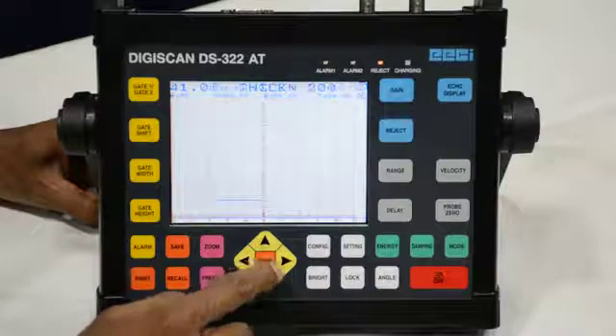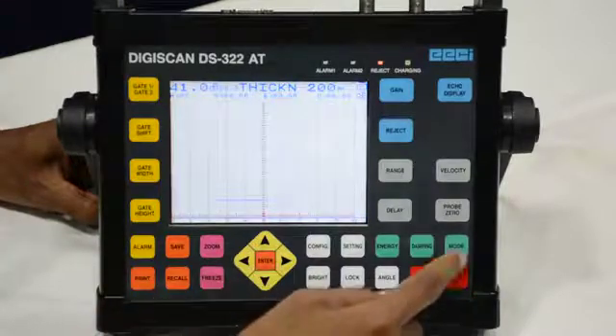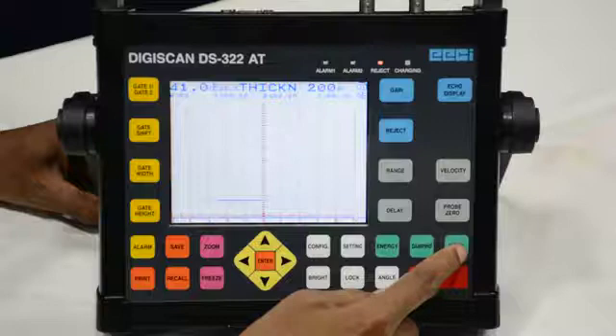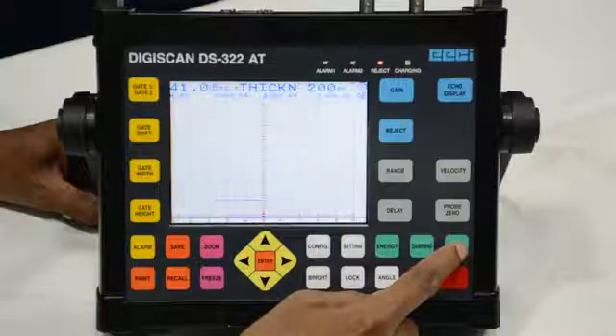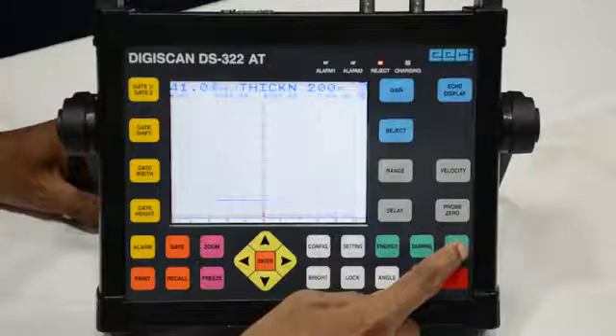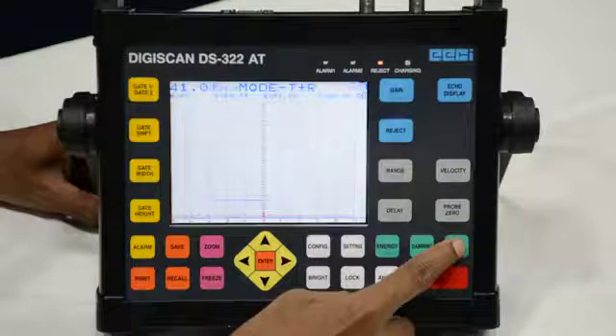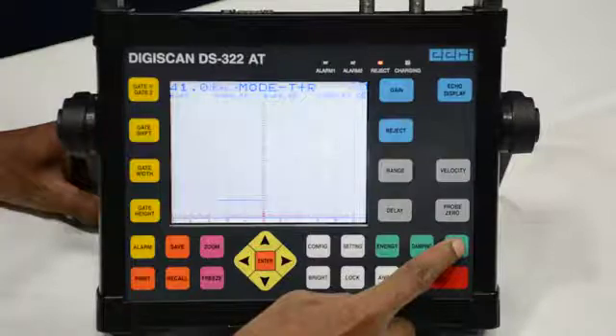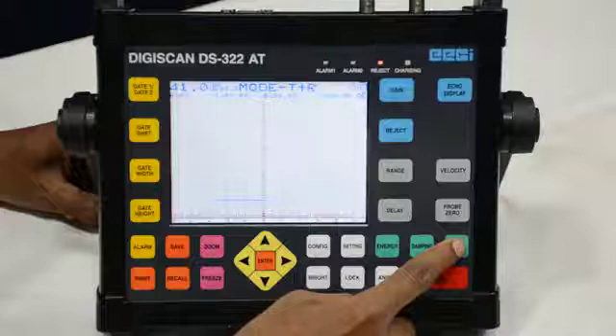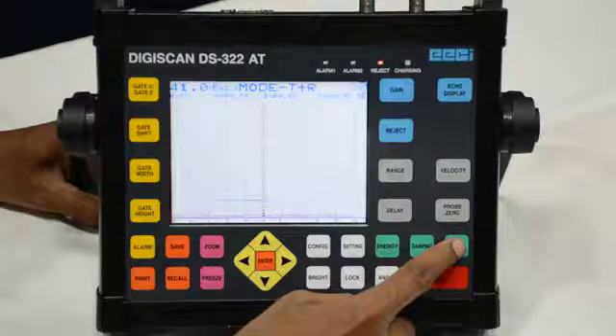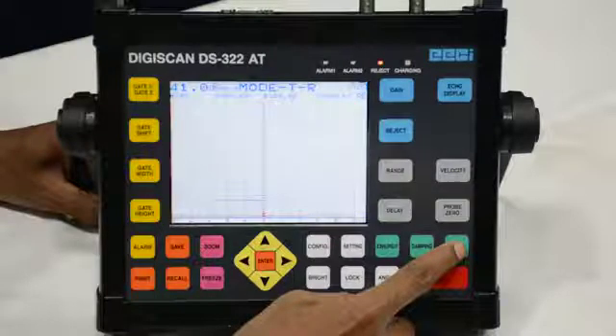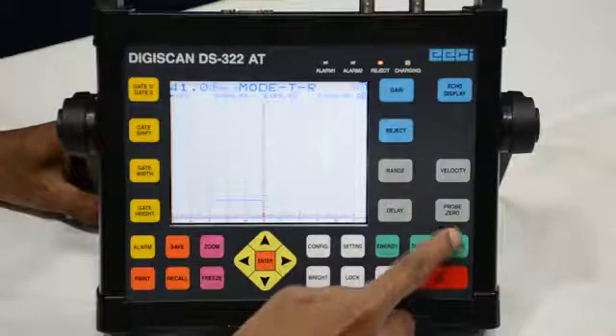Next we have to see which probe we are using — probe as per crystal. There are two types: single crystal and double crystal. This is the mode button. If we are using a single crystal probe, we have to make the mode T+R, meaning the same crystal will transmit and receive. If it is double crystal, we press again and the mode will convert to T-R.